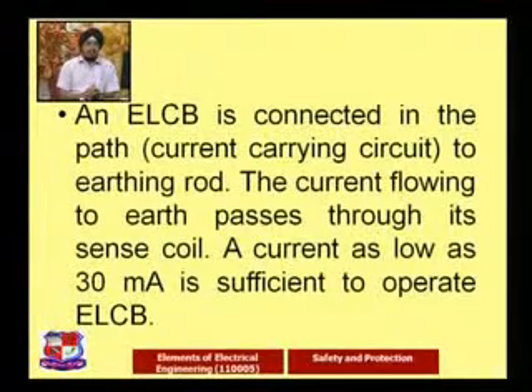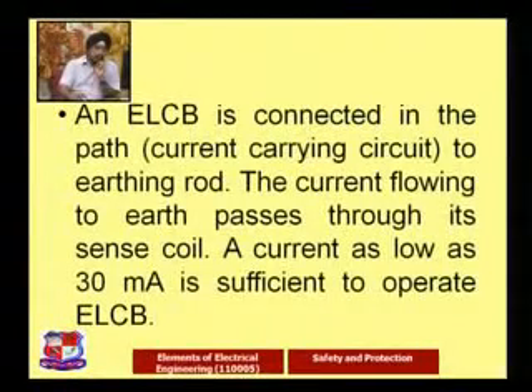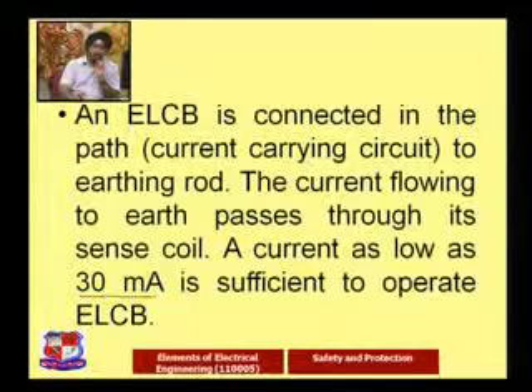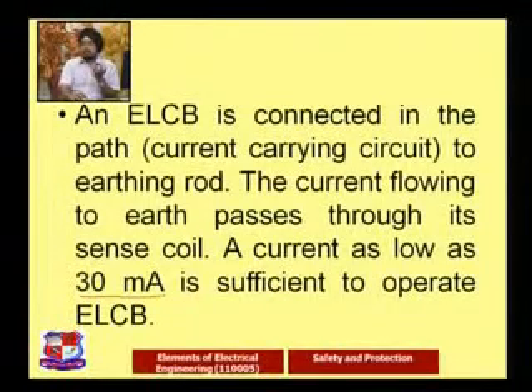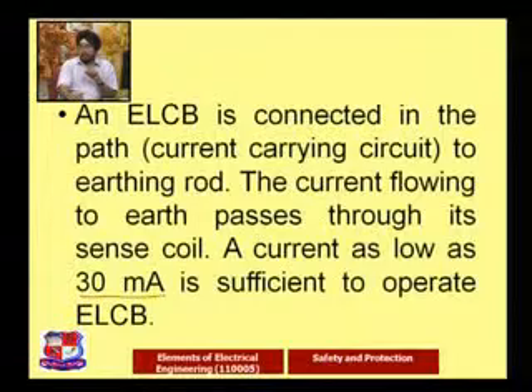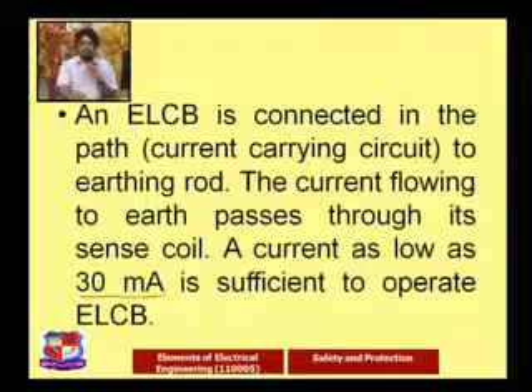Now an ELCB is connected in the current-carrying path to the earthing rod. The current flowing to the earth passes through its sense coil. A current as low as 30 milliampere is sufficient to operate the ELCB. This 30 milliampere current may not be sensed by the fuse or MCB, or is not enough to operate them. But that leakage current, that fault current, can cause harm outside. So we don't want to take the chance, and that's why the ELCB plays the major role in that particular case.